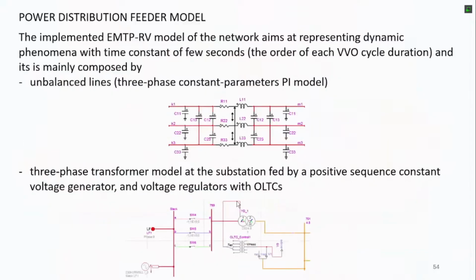And these are the details of the distribution feeder nodes with the typical representation of the lines, and here below, the transformer with on-load tap changers. We have considered 20 seconds of delay for each action of the transformer, a mechanical delay plus an increased delay.